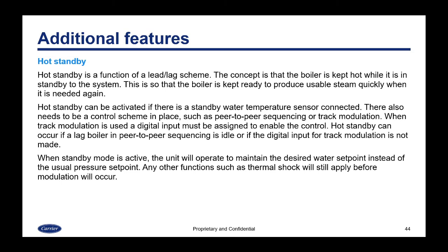When track modulation is used, a digital input must be assigned to enable the control. Hot standby can then occur if a lag boiler in a peer-to-peer system is idle, or if the digital input for track modulation is not made. That means when the BMS system does not need that boiler to run, you can activate hot standby so that it can turn on. When standby mode is active, a unit will operate to maintain the desired water set point instead of the usual pressure set point. Any other functions such as thermal shock will still apply before modulation will occur.